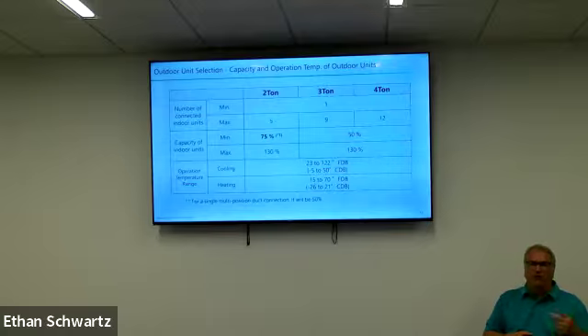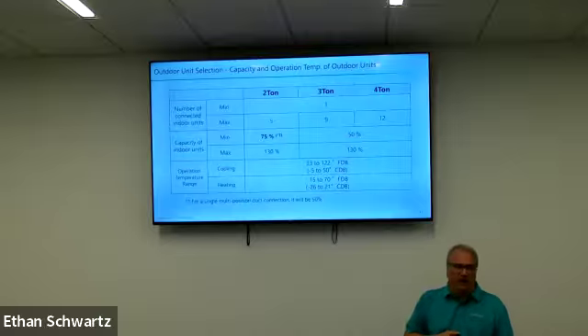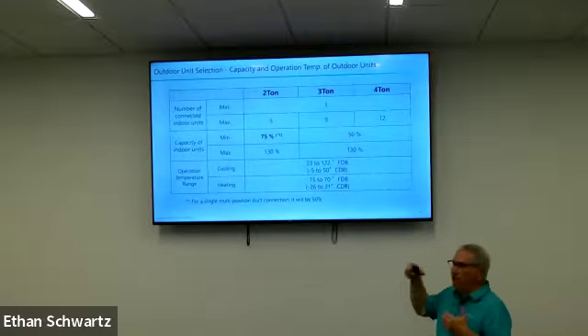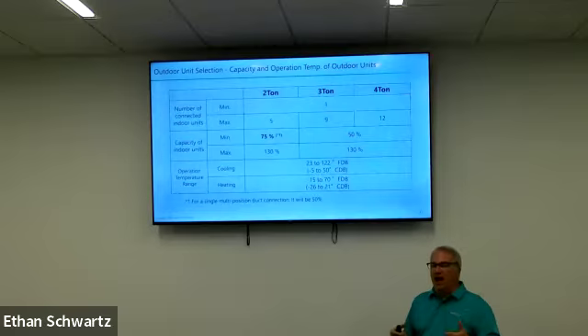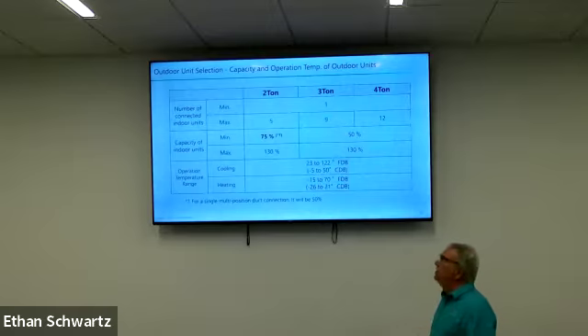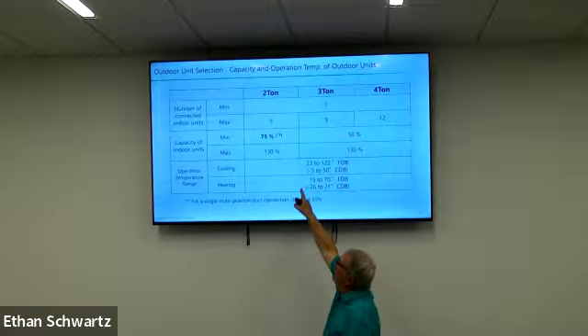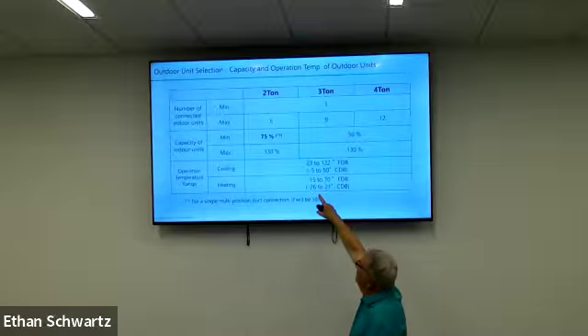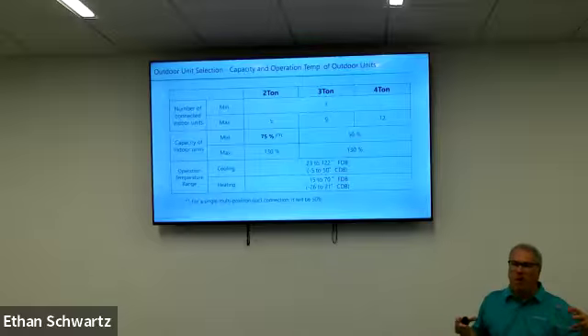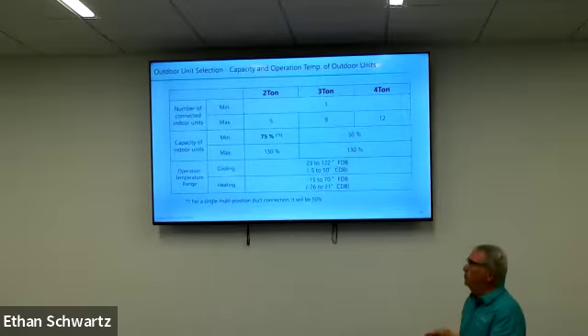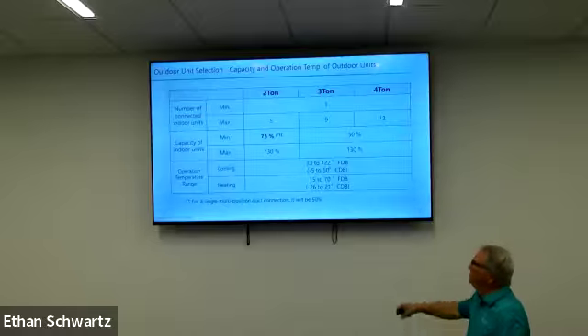Multi-family residential. One of the requirements in multi-family residential is that they want individual power metering. So they need something small enough, but we've got to have something with long enough line set lengths. We've got to have something that can handle a long up, long down from the indoor unit to the outdoor unit. And we need to be able to handle 12,000 BTU and 18,000 BTU connections because of the heat loss and heat gain of the typical apartment or condo. So that's why, for a single multi-position duct connection, which we're just coming out with, the multi-position units, we can go down to a 50% connected capacity.